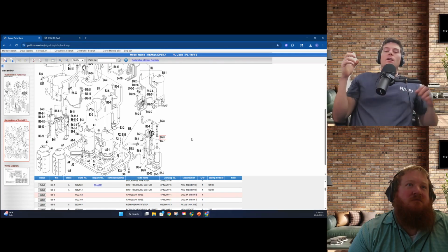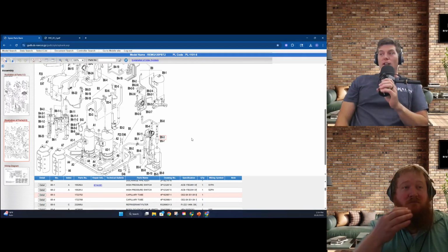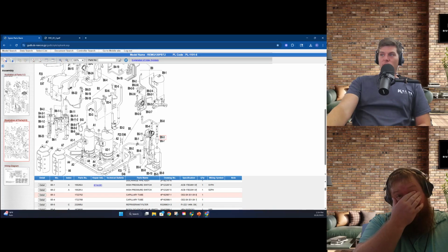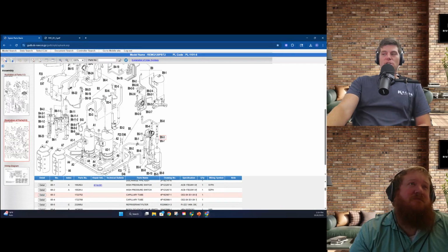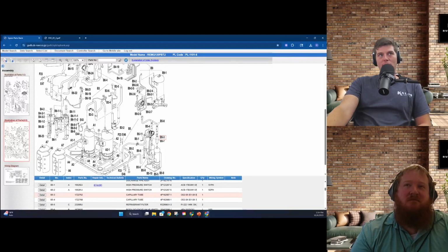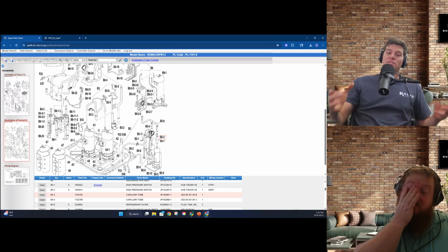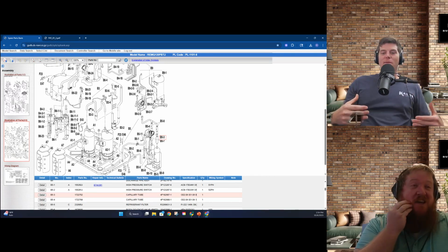And so what happens to cause the oil line to break? Well, it's connected to the suction. If you look right here, the N and the O at the top, those are right on the suction connections of the compressor. So when the compressor bearings fail due to a lack of lubrication, liquid slugging removes oil, which causes the bearings to overheat because of the lack of oil. That causes the shaking, and you get excessive vibration.